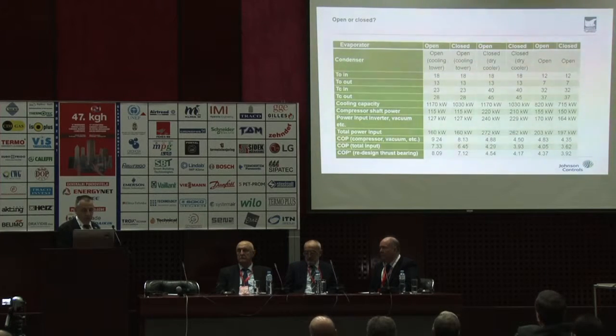And here we have the possibilities for making 13, 18 degrees with the evaporator either as a closed loop with an extra heat exchanger between, or the condenser, the same dry cooler or open, and you can see that the COPs will be affected with the extra heat exchanger. But it has, of course, other benefits. And in the field test system now, because the water that we take in from the bore is full of iron, and the process we are cooling doesn't like minerals in the water, we have to have this additional closed loop water for the machinery, and then we have closed the evaporator, so it becomes a closed circuit.